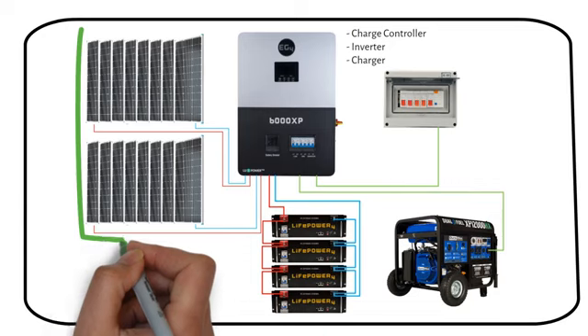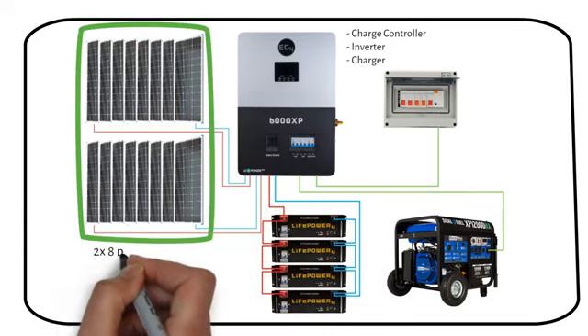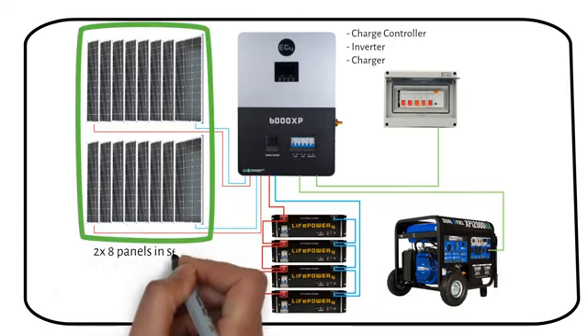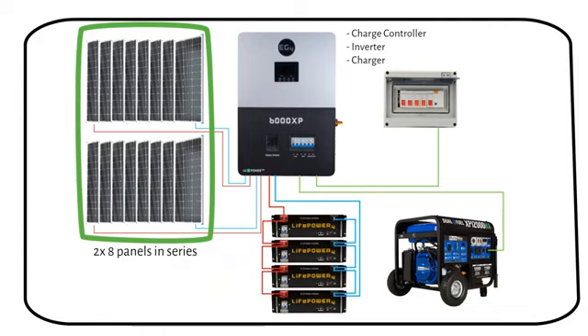We have two large arrays of solar panels, each consisting of 8 solar panels in series. With more panels, the system can generate enough power to run a home completely off-grid. The maximum input voltage of the hybrid inverter is 480 volts, and it has 2 separate MPP trackers, perfect for connecting 2 solar arrays. We don't need a combiner box or a solar disconnect switch, because it's already integrated on the right side of the device.